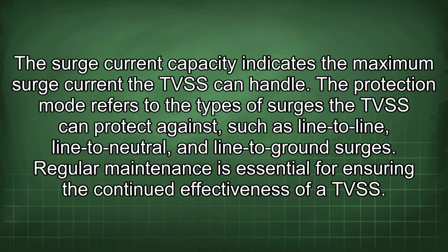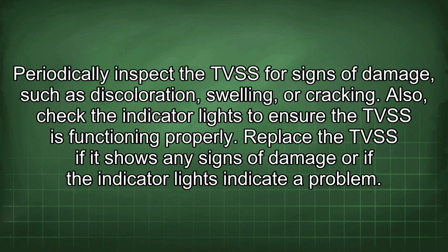The protection mode refers to the types of surges the TVSS can protect against, such as line-to-line, line-to-neutral, and line-to-ground surges. Regular maintenance is essential for ensuring the continued effectiveness of a TVSS. Periodically inspect the TVSS for signs of damage, such as discoloration, swelling, or cracking. Also, check the indicator lights to ensure the TVSS is functioning properly. Replace the TVSS if it shows any signs of damage or if the indicator lights indicate a problem.